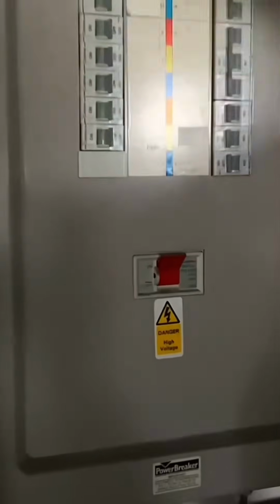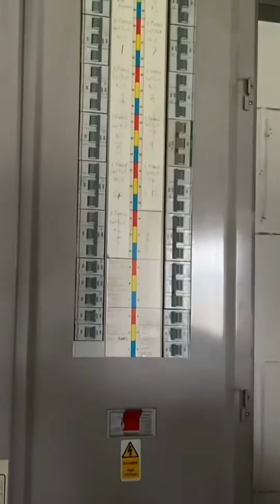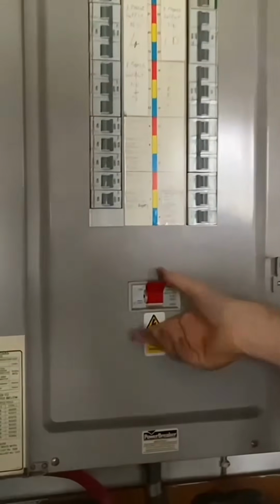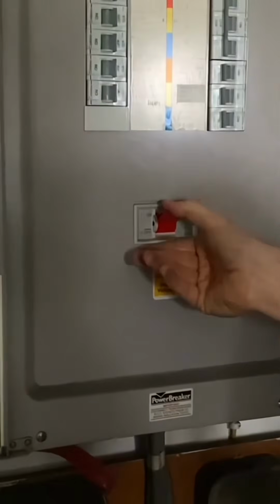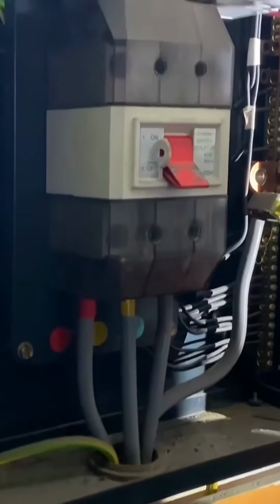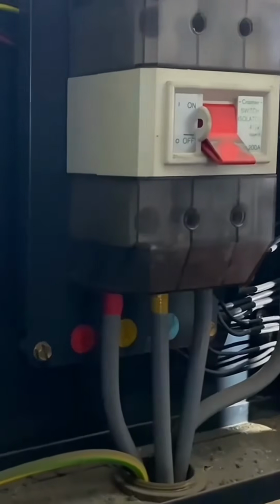And so that looks like all the loads have been taken off. Yeah, and we're going to do the main switch now. Now it's quite happy just to turn the main switch off. The board's off, the cover's off, and we're now going to carry out the external earth fault loop test. Just remind me why I'm going to disconnect the earthing conductor, which is here. Okay, so yeah, it is the main earthing conductor.